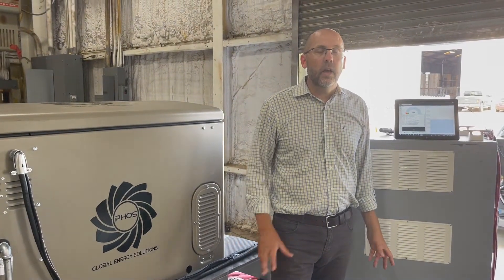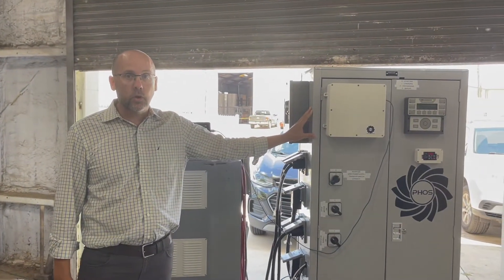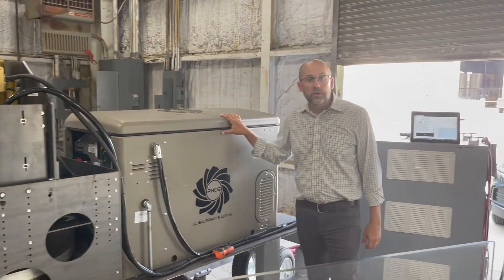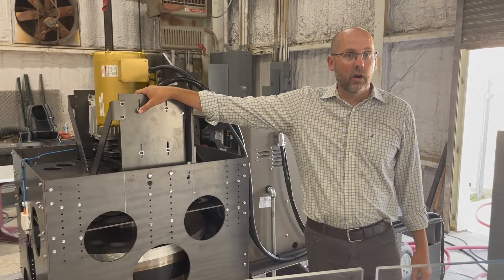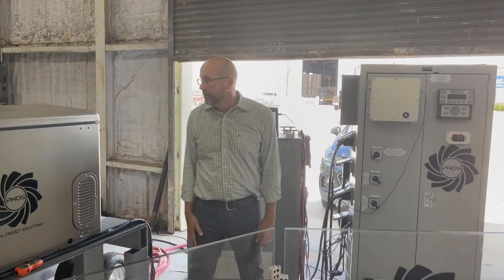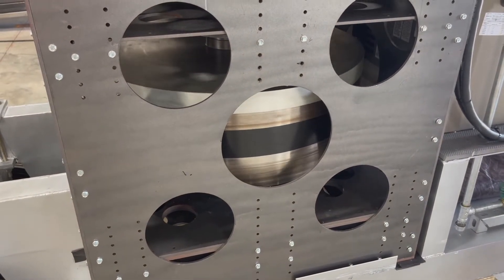Now we're going to simulate a scenario where power fails. In this case, we have a mock-up for the grid. That grid is being monitored by our controller. That controller will sense when the grid fails and initiate backup power generation to bring our flywheel up to speed. Once that flywheel is up to speed, this emergency generator will shut off, and all energy will be generated directly from the electrical generators on the PHOS system. The PHOS system, sensing the power failure, signals the generator to start. Once up to speed, sufficient energy is being generated and the contacts close, sending power to the drive motor and spinning the flywheel.